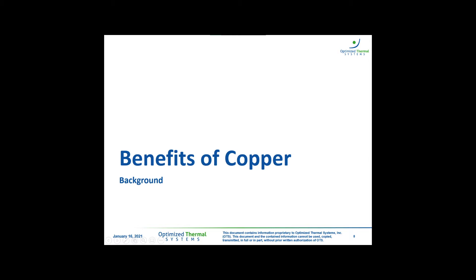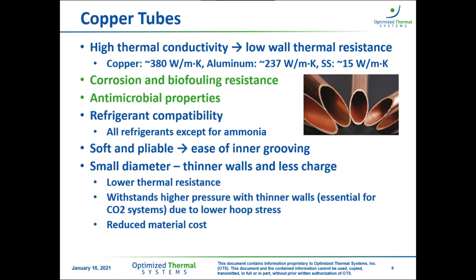Why do we use copper tubes in heat exchangers? The heat exchanger's primary job is to transfer heat, so we want a material with relatively high thermal conductivity. Copper has high thermal conductivity compared with other common materials such as aluminum or stainless steel. High thermal conductivity gives us low wall thermal resistance and improved heat transfer between the working fluid inside the tube and the air on the outside. Copper also has natural antimicrobial properties that help it resist corrosion and biofouling.